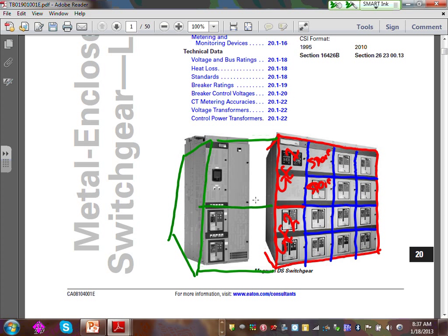That particular section is going to be for the main circuit breaker, and this for the CTs. That's what I would like you guys to draw. So you bring the CTs, current transformers, and metering equipment right here. Then you put your main circuit breaker. That's going to be a 4,000 amp, right? This is going to be a 4,000 amp. And you feed the whole switchgear.